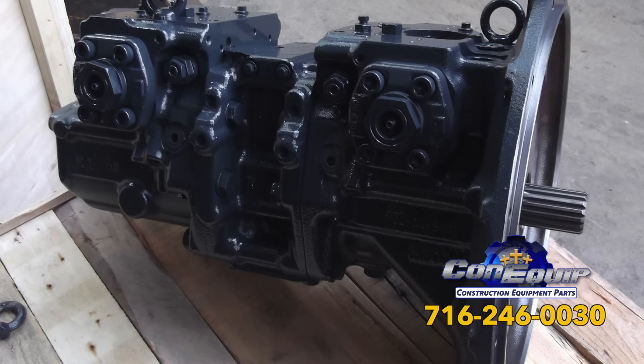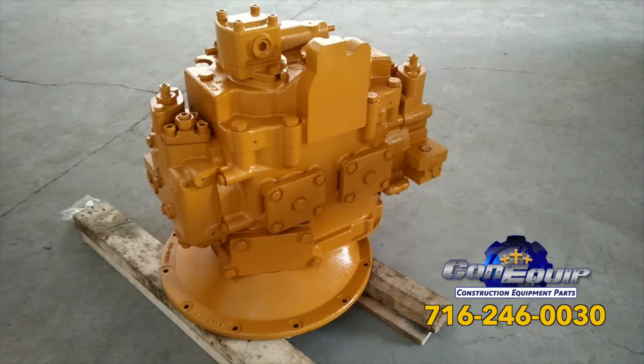Hydraulic oil changes should be reserved for when base oil degrades or when oil additive depletion has occurred. Make sure your hydraulic oil is being filtered properly to consistently remove contaminants. Keep in mind, increased heat gradually reduces the effectiveness of hydraulic fluid and will eventually damage components. So, if your system is getting hotter than it should, shut down the machine and investigate the problem immediately.